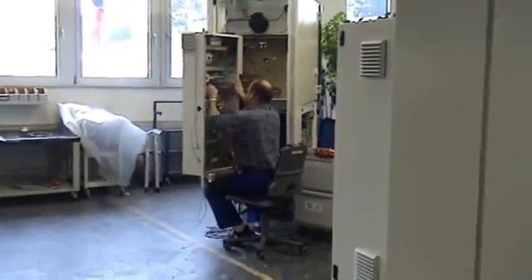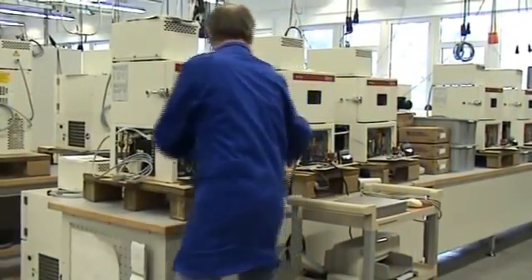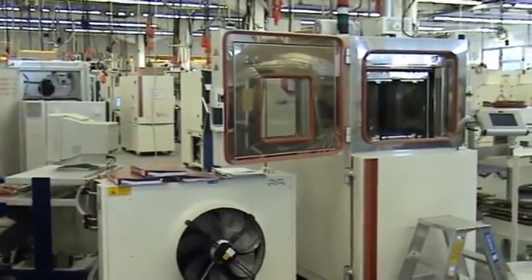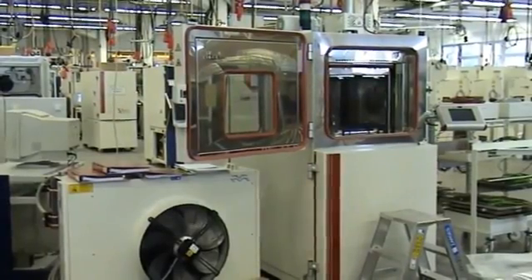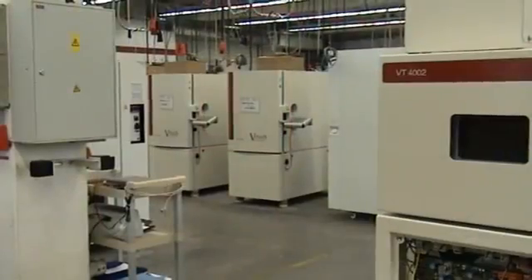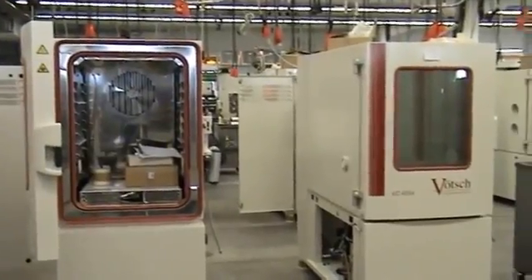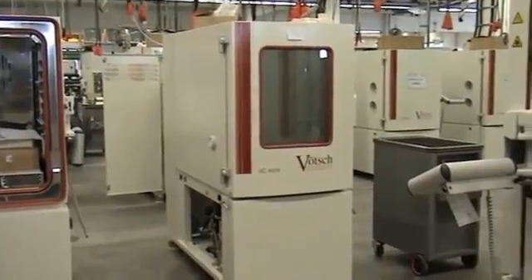Now the chamber is ready for its first performance test in the test area. Every Votsch chamber is tested and the performance data is documented. The chambers are equipped with temperature and humidity sensors. During predefined temperature and climatic tests, performance data are recorded and archived for each of the 1,500 chambers annually produced at Votsch.